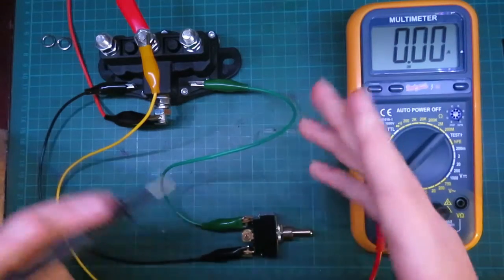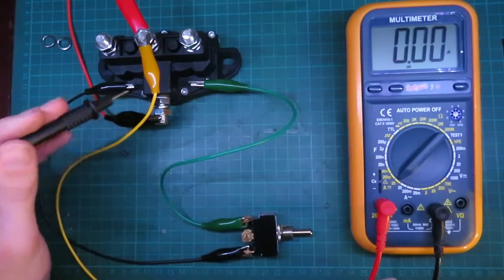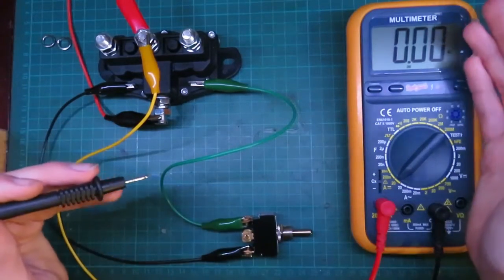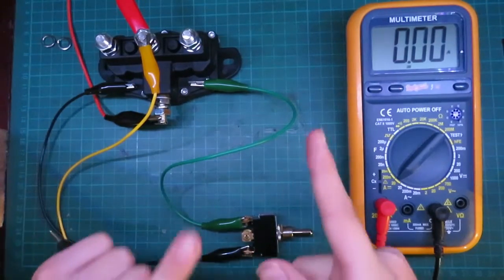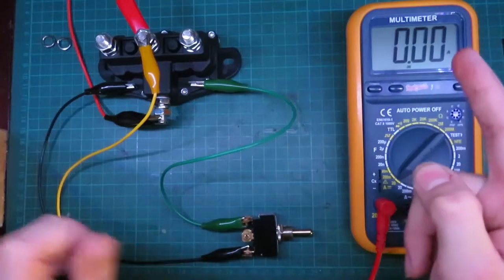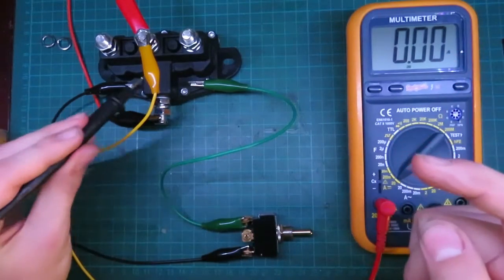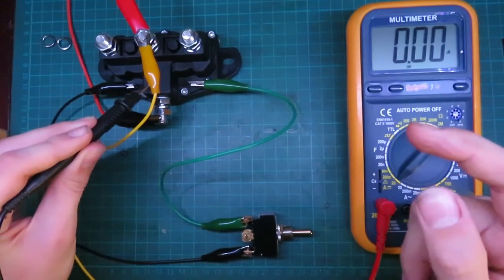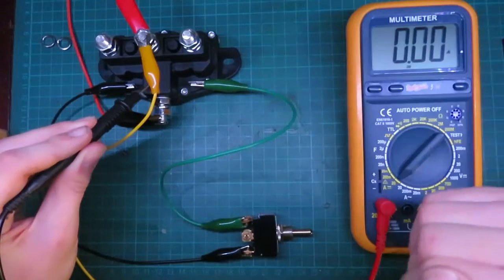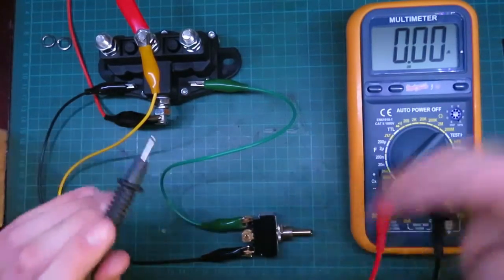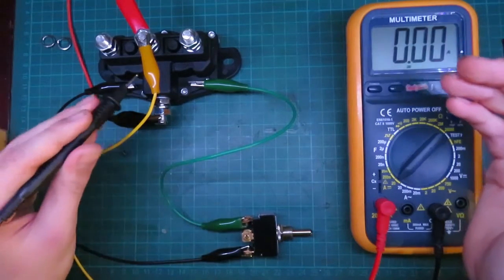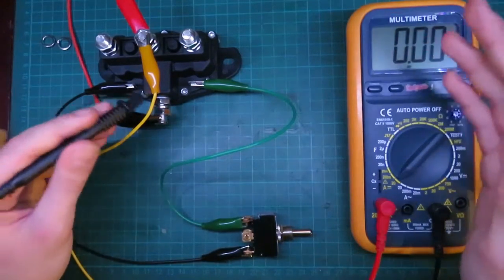You might be wondering why one way draws more current than the other way. Well, there's two coils in here pulling the solenoid either the one way or the other way. One coil might have to do slightly more work in order to pull over. Maybe one coil has a little bit less resistance than the other coil, so it can draw more current. I'm not really sure, but it's probably one of the two reasons there.